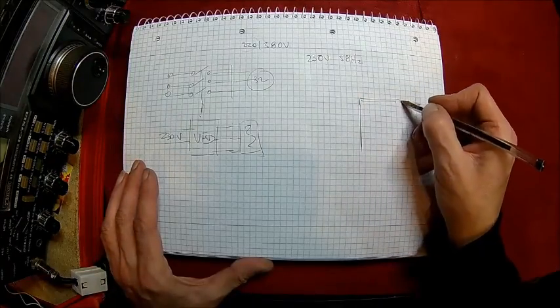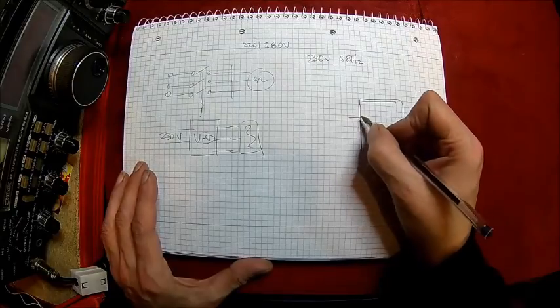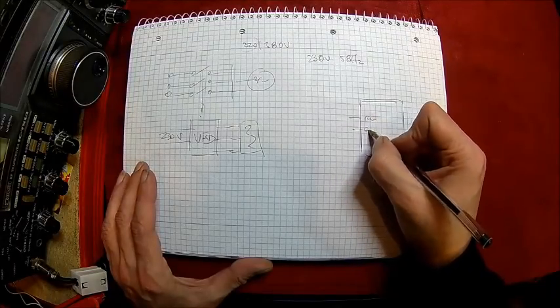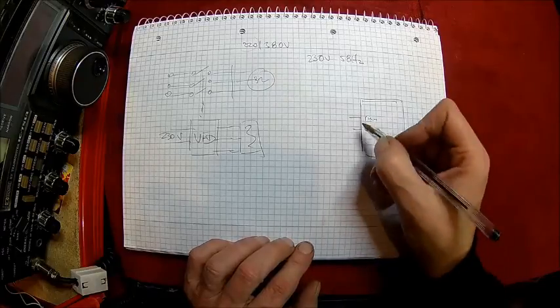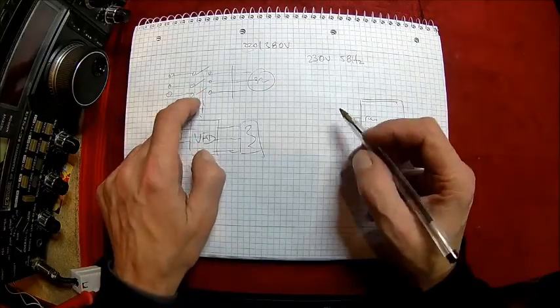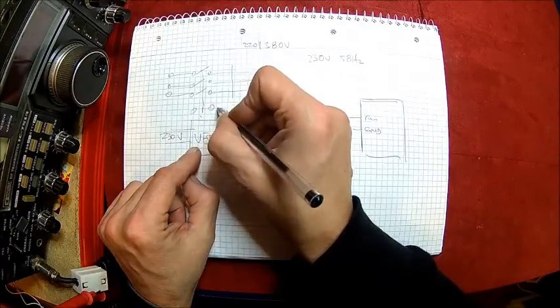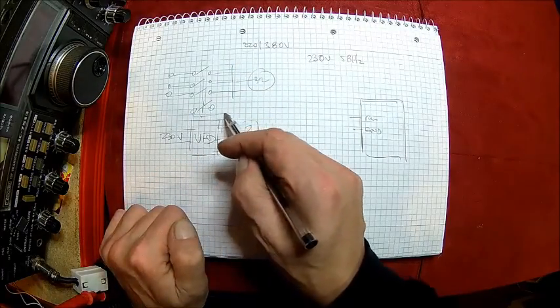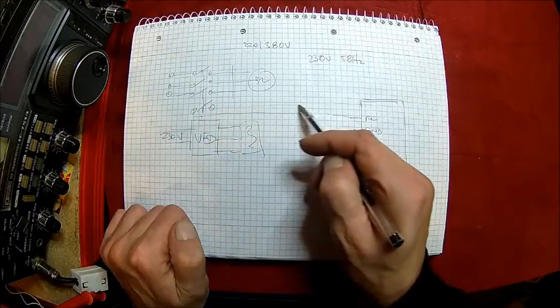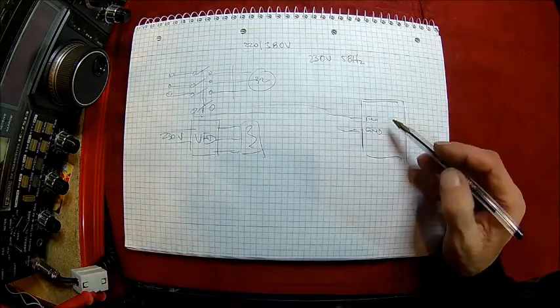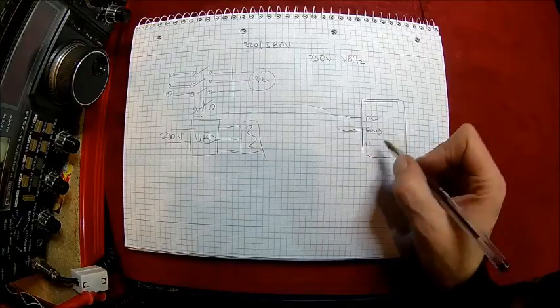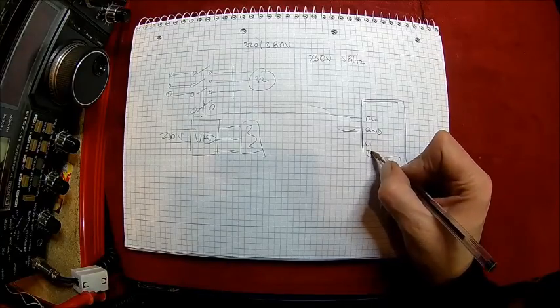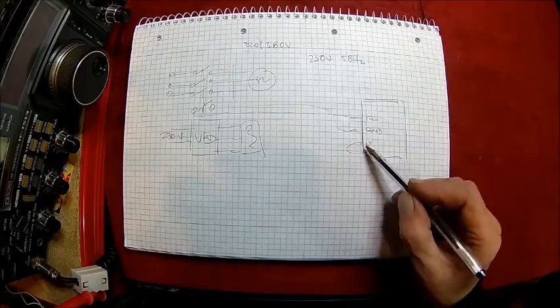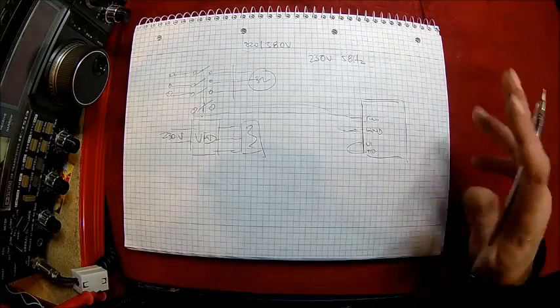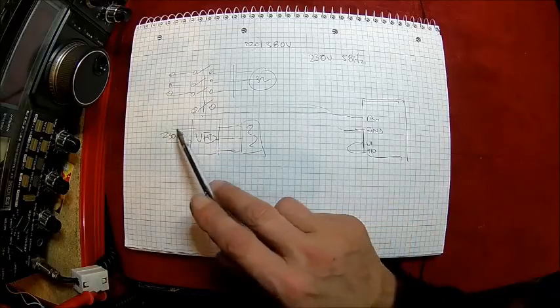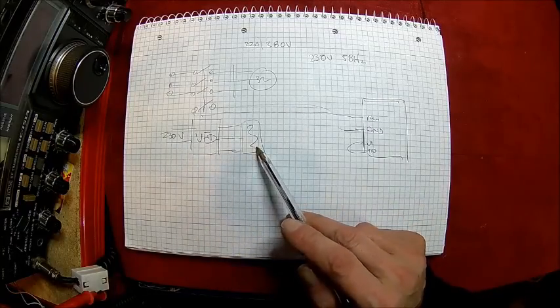Our VFD has a run input, run and usually ground, and all we do is using that contactor, which has an auxiliary contact down here, and we use that and connect it to this end. We also have on this one, it's VI and plus 10, which we just bridge. So the inverter always runs on full power. We talk about the parameters later.